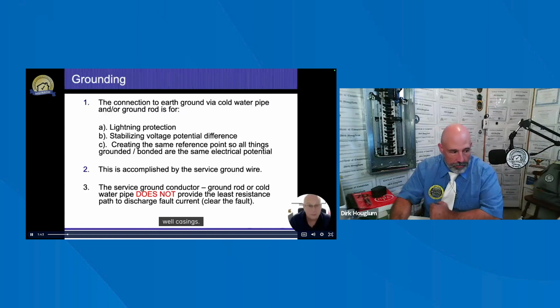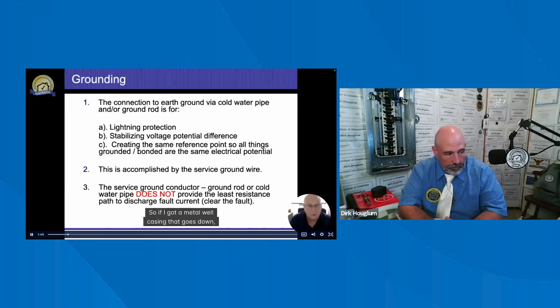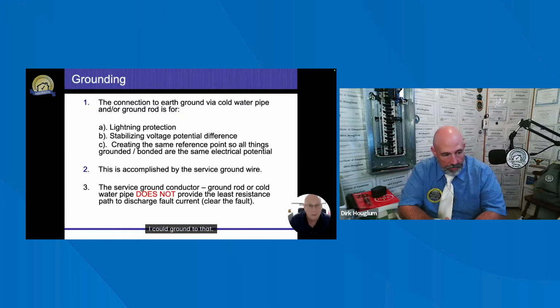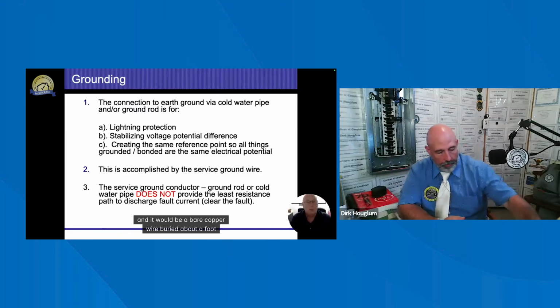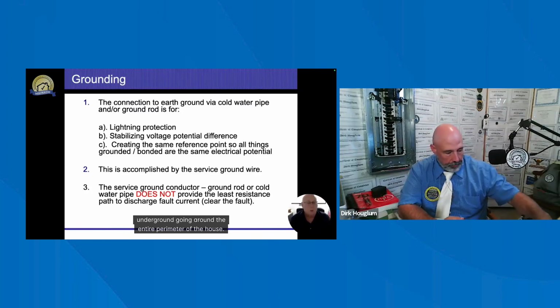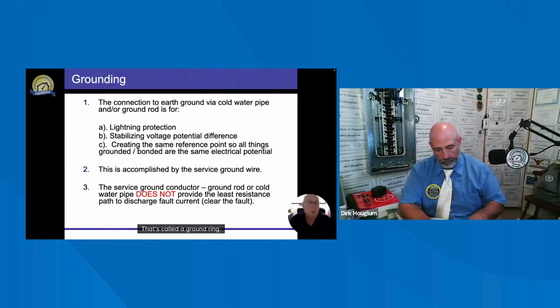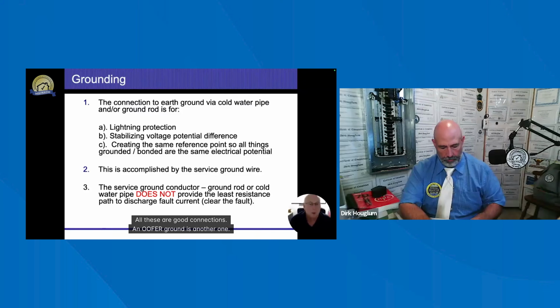Well casings. So if I have a metal well casing that goes down, I could ground to that. I could do something called a ground ring. So I would take a number 6 or a number 2, depending on the size of the electrical system, and it would be a bare copper wire buried about a foot underground going around the entire perimeter of the house. That's called a ground ring. A ground plate is basically a 4x8 sheet of metal laid flat, covered in dirt. All these are good connections. A Ufer ground is another one.